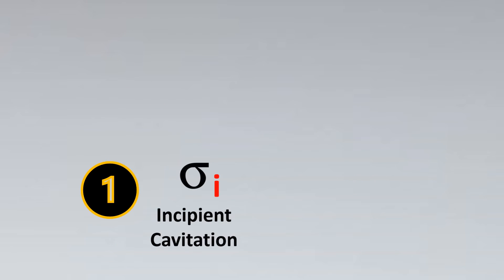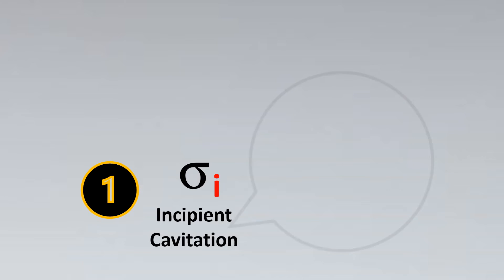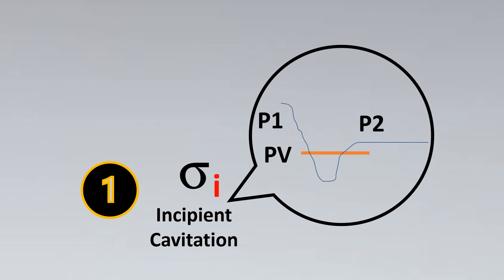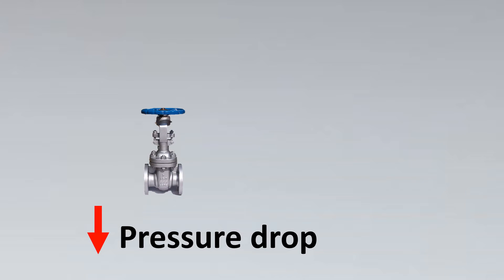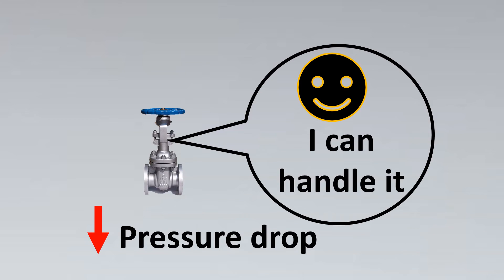The first one is incipient cavitation. The word incipient itself means start of something. This is the very start of cavitation. Because it's just the incipient stage, the pressure drop is very low for such cases, and the valve says that it can handle it. We don't need to have any special precautions for such a case.